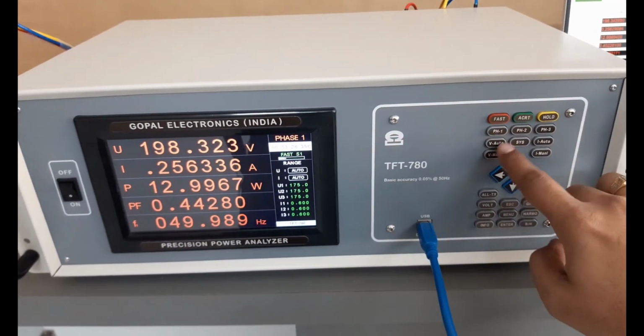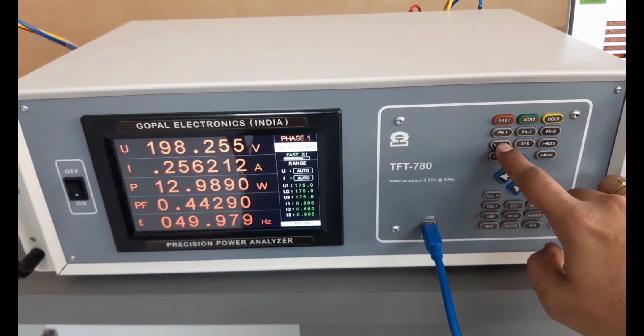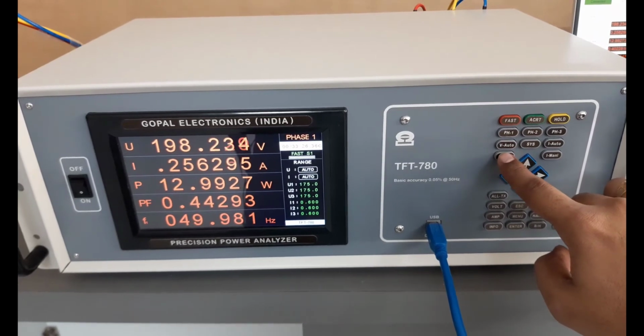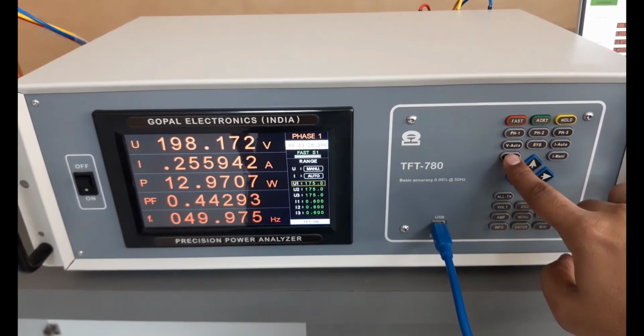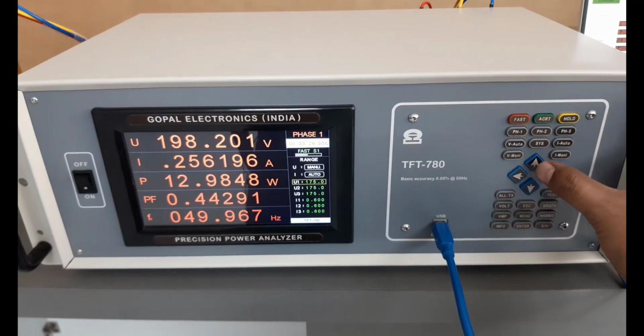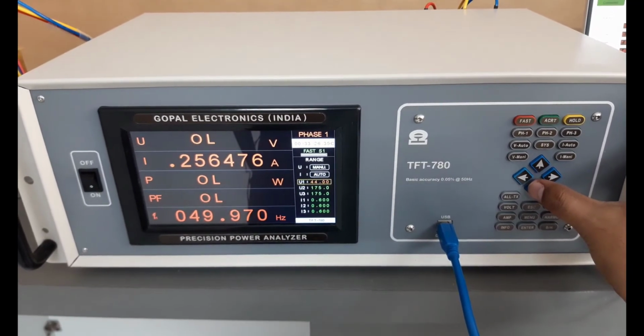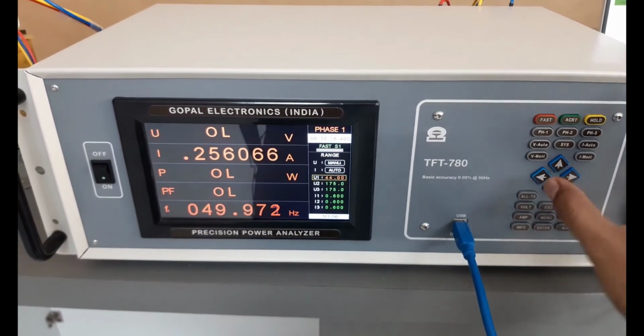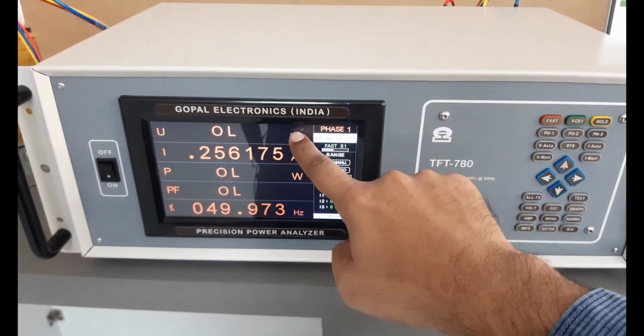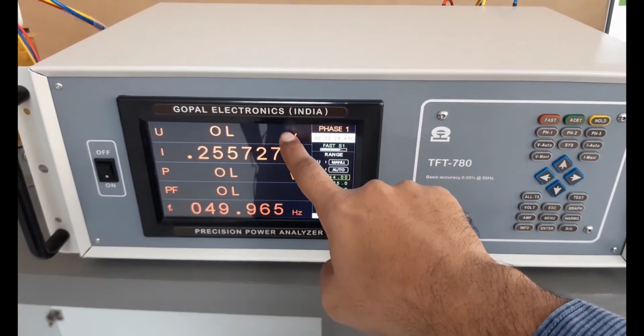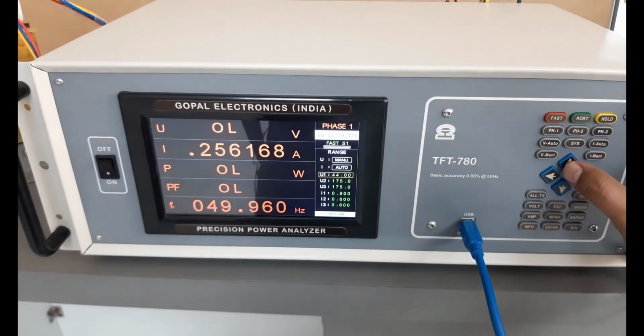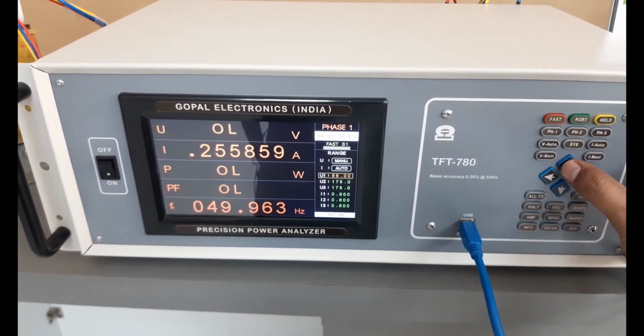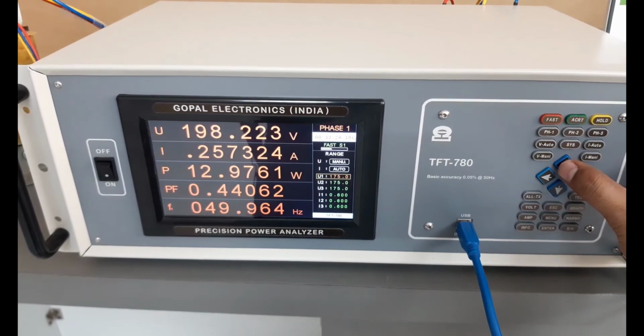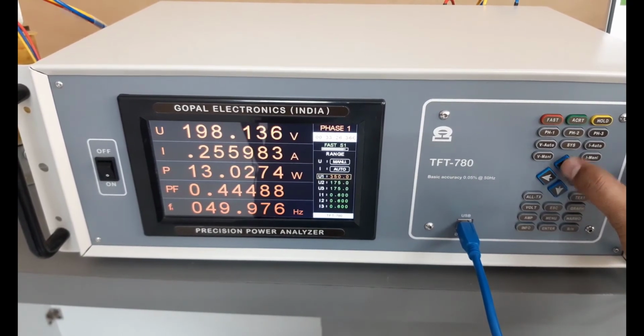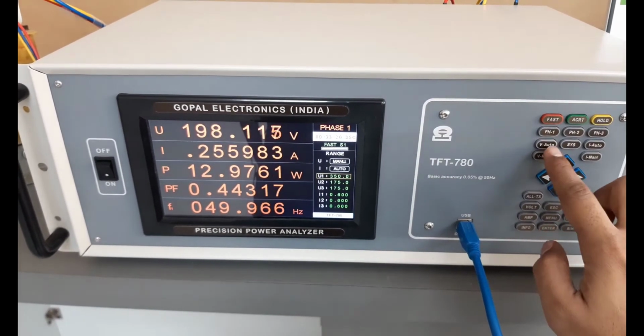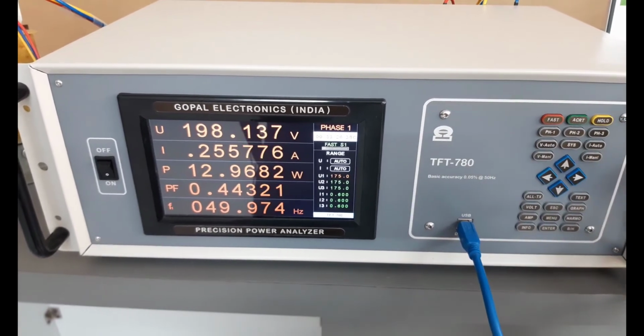Now these are the voltage range key. Either you want to put in a auto range, or in a manual range. Suppose you select manual, by up down you can change the range. Now I have selected 44 volt range and voltage is higher than 44 volt, so that's why it is showing overload. 88 volt range, 175 volt range, 350 volt range. So that way we can put in V auto.